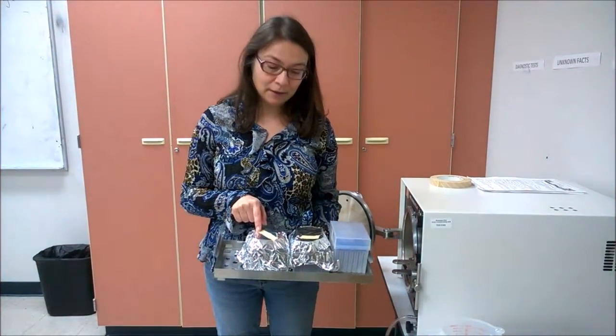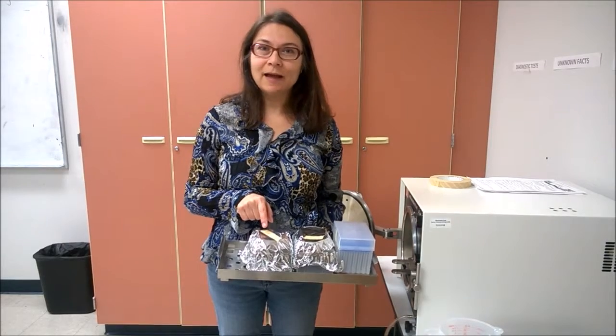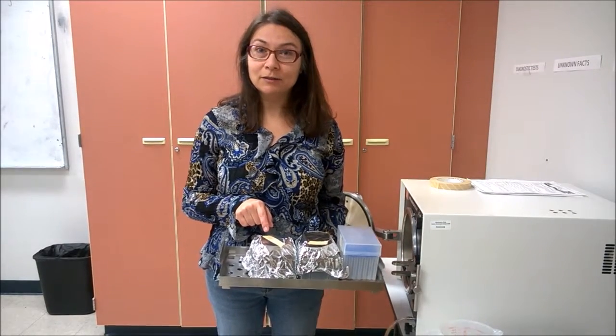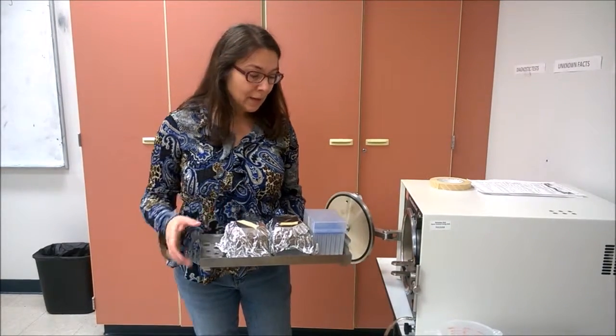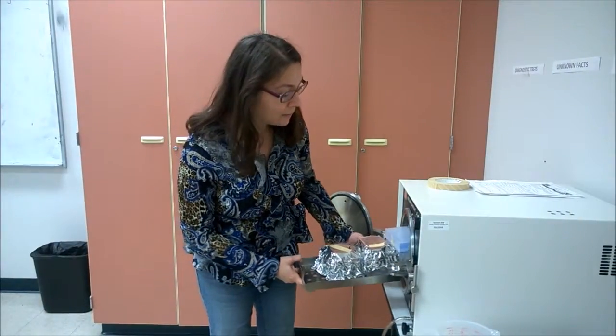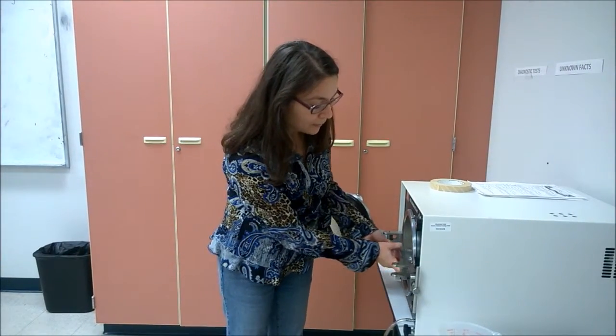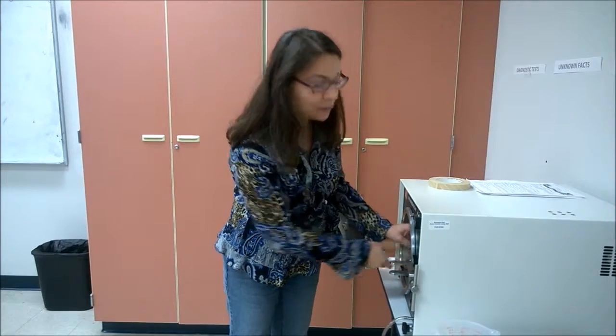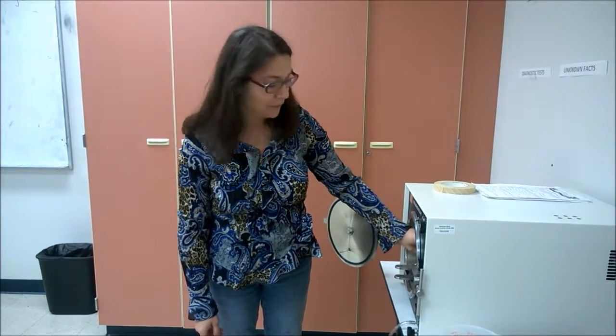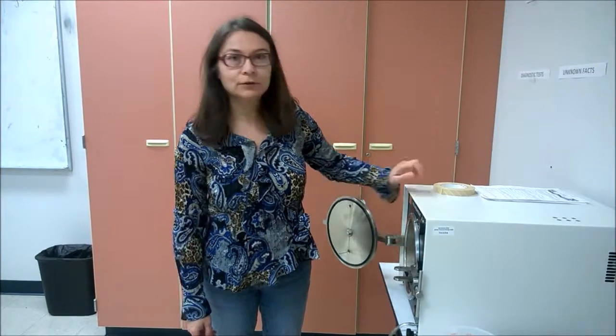The piece of tape is used for making sure that the autoclave reaches the correct temperature and correct atmospheric pressure. In addition to the atmospheric pressure, it needs to reach 121 degrees Celsius and 15 psi. And the sterilization will occur in about 20 to 25 minutes.